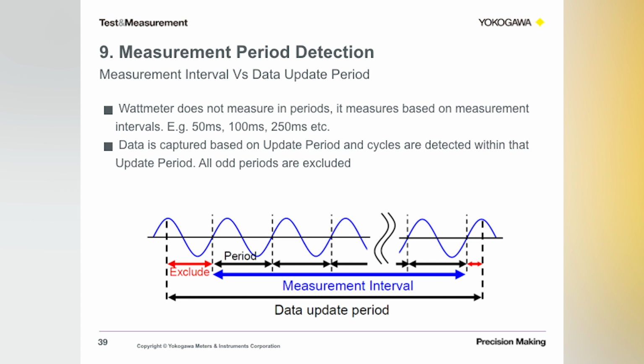So how does a power meter or a power analyzer measure this period? Well, it doesn't. It actually measures based on measurement intervals. On Yokogawa power analyzers, this measurement interval setting is provided via the update rate setting, which can either be set to 50 milliseconds, 100 milliseconds, 250 milliseconds, and so on. The instrument determines the measurement interval within this update rate by determining the correct period of the incoming signal. Once the period is detected, the integer number of cycles are detected within that data update period, and those cycles are used to actually calculate the RMS values of power, voltage, and current. All right. So I hope that's clear.